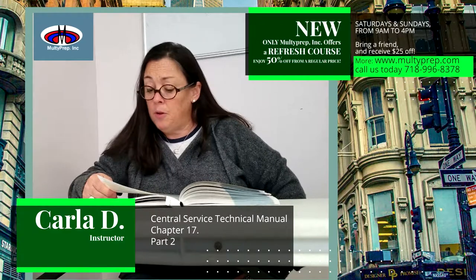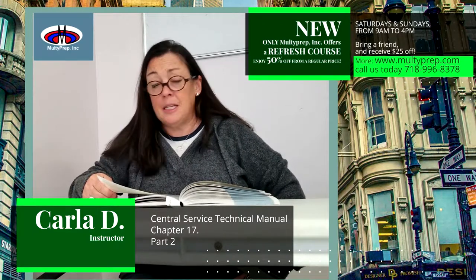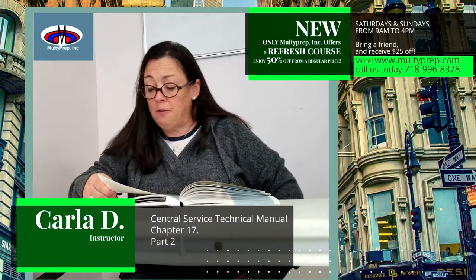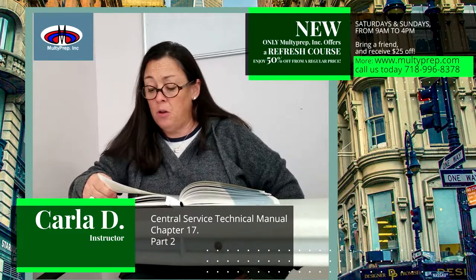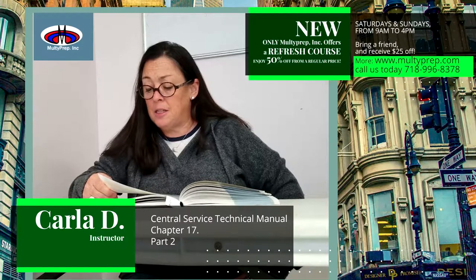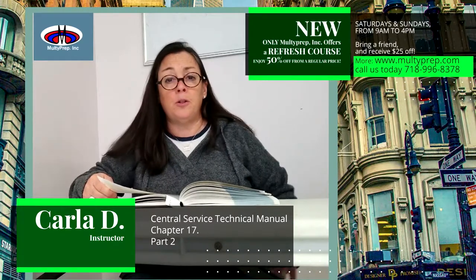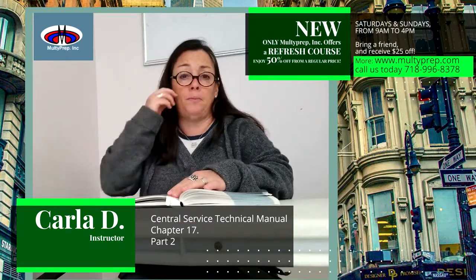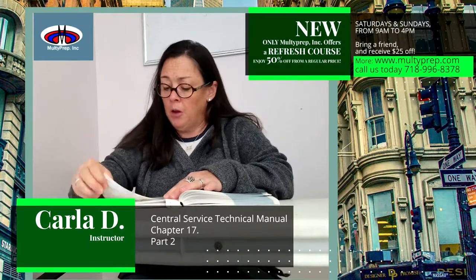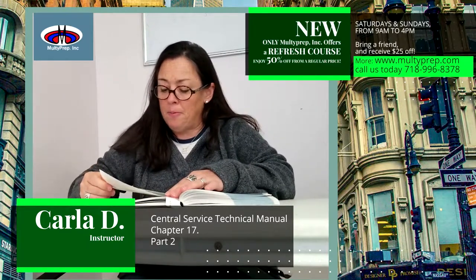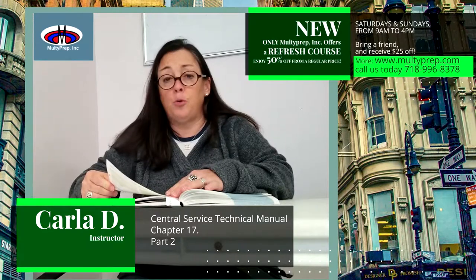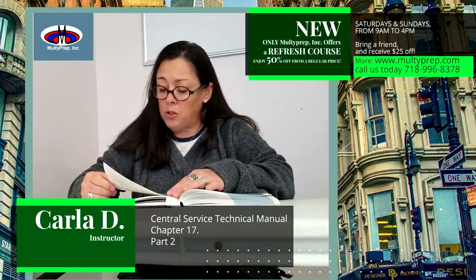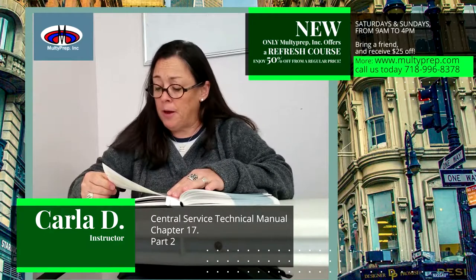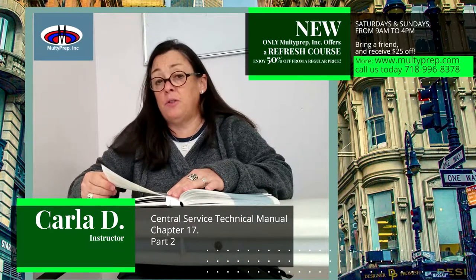For example, if a manufacturer has validated a device to be steam sterilized in a 10-minute, 270-degree Fahrenheit cycle, a facility cannot test this item in a 5-minute, 270-degree Fahrenheit cycle. Healthcare facilities do not have the proper products or equipment to properly test and ensure the item is sterile in the shorter cycle. Also, the FDA has approved the manufacturer's cycle, not the healthcare facility's cycle.